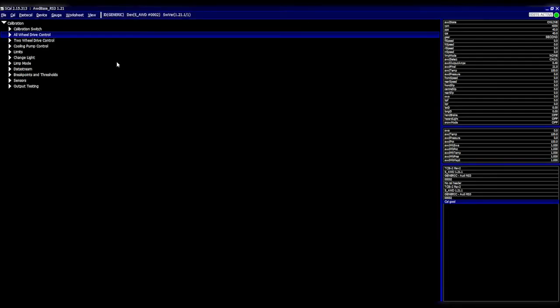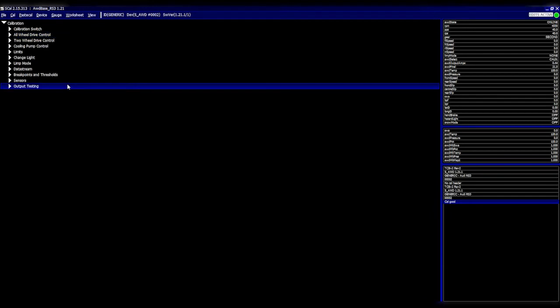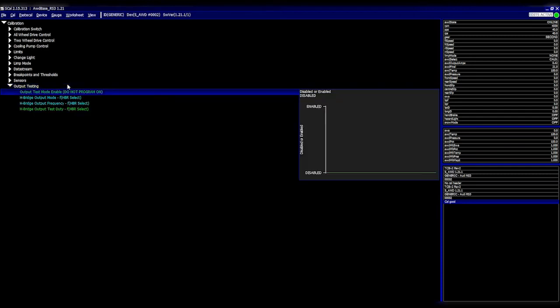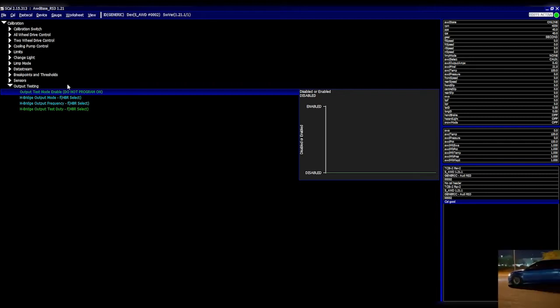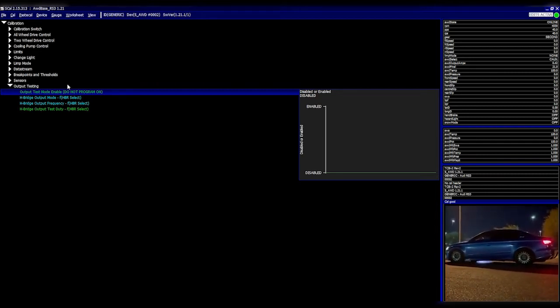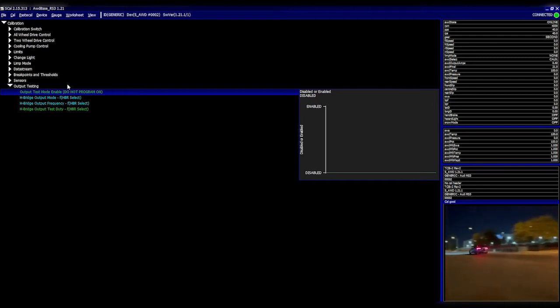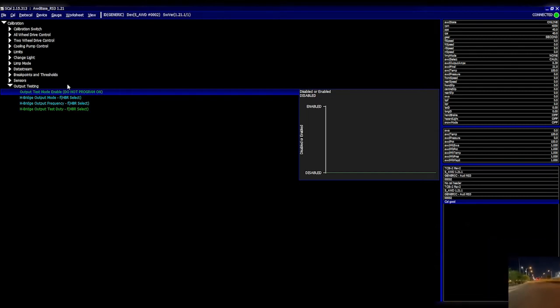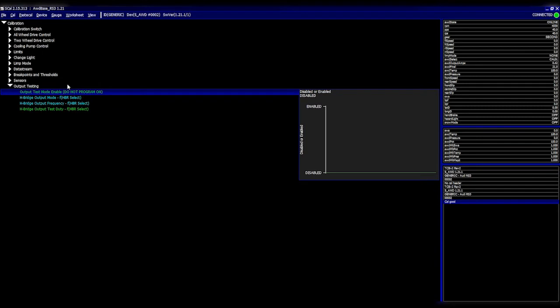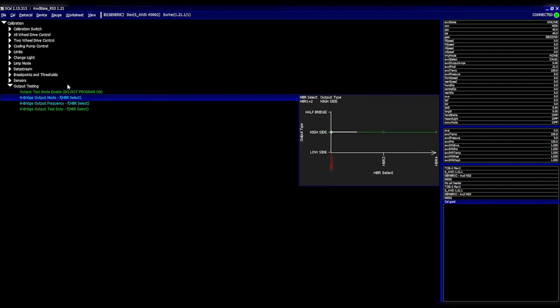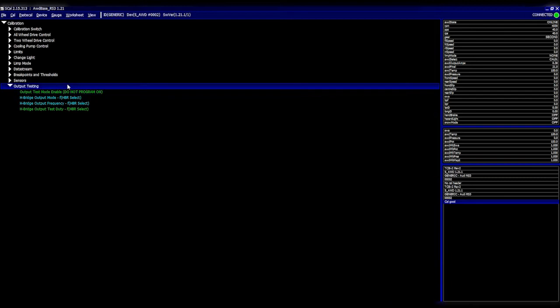The first one that's probably noticeable is that you've now got output testing. The output testing is quite useful because it allows you to fault find a problem. You can enable the output test mode that turns off all of the logic of your drive controller. You can set your output test mode to low side, high side, half bridge, a set frequency and a test duty cycle. It's quite useful to be able to do some testing now.